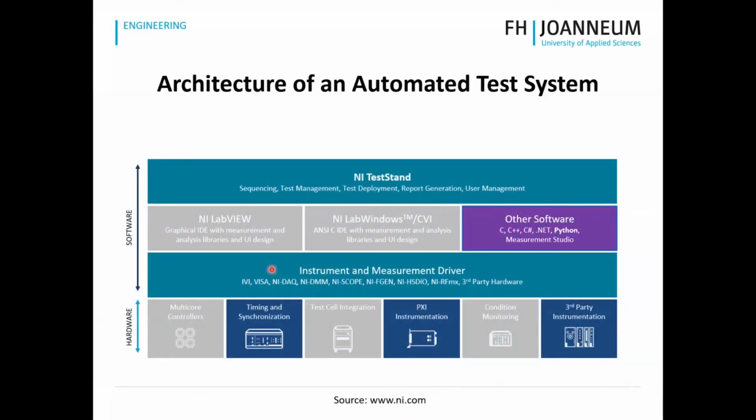So the concept and architecture, I think you all know or have seen this picture before. We follow the same approach, since this seems to be also widely accepted in the industry, that there is on the top layer a sequencer with NI TestStand, and then there are code modules developed in any kind of software interacting with instrument drivers, which are in the end interacting with instrumentation and performing the interaction. For today, we're just going to focus on the other software and a little bit on TestStand, not so much on the instrument driver and on the instrument itself.